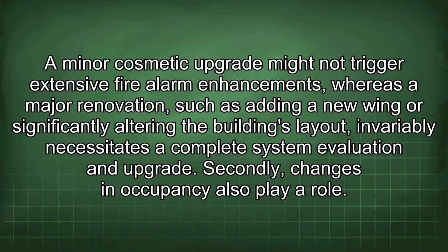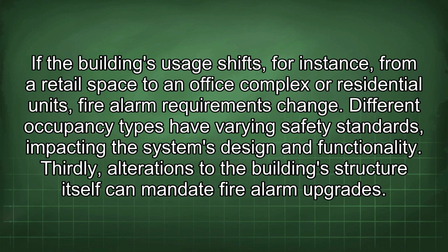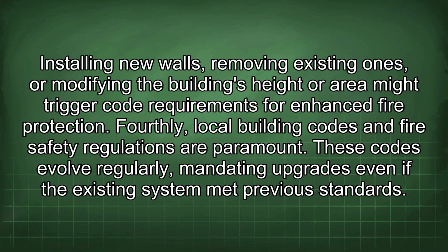Secondly, changes in occupancy also play a role. If the building's usage shifts, for instance, from a retail space to an office complex or residential units, fire alarm requirements change. Different occupancy types have varying safety standards, impacting the system's design and functionality. Thirdly, alterations to the building's structure itself can mandate fire alarm upgrades.